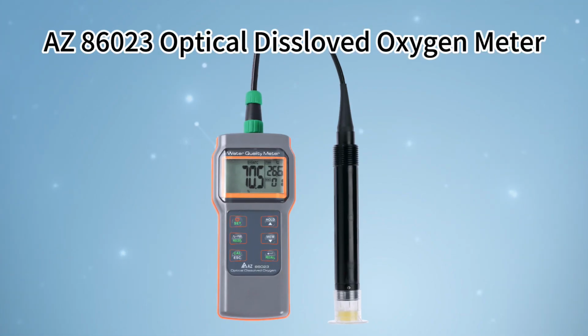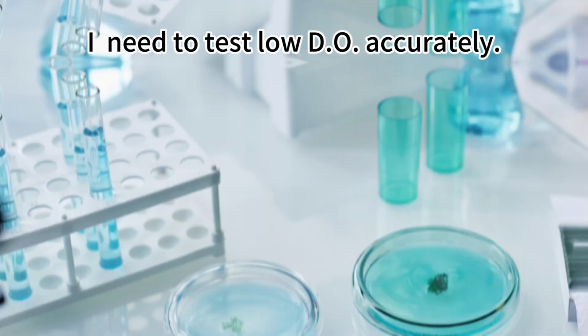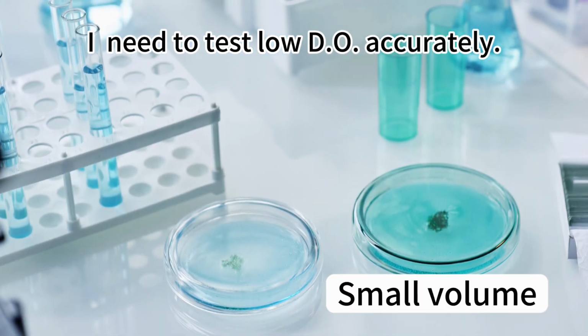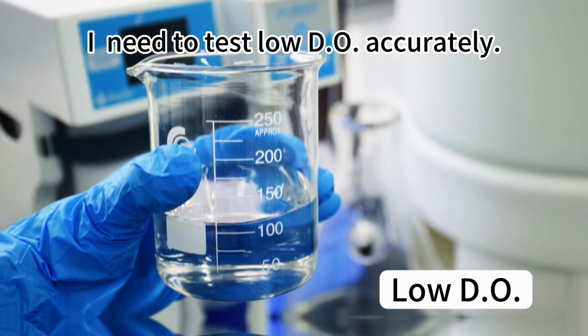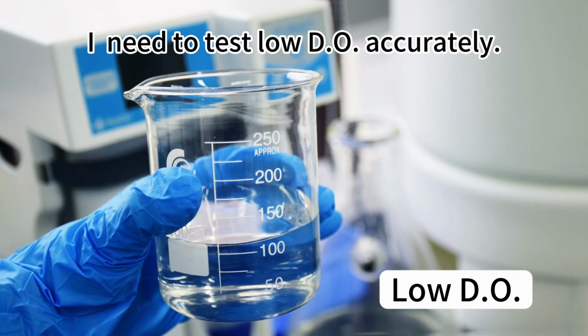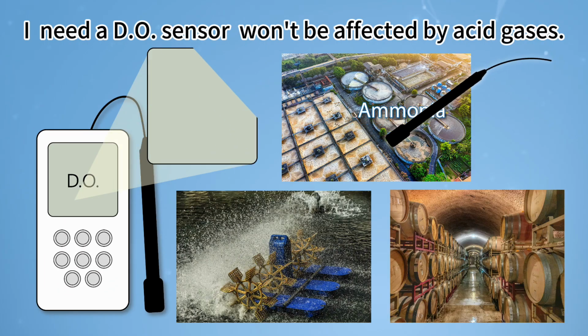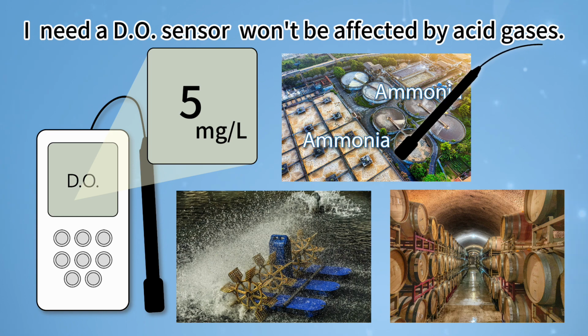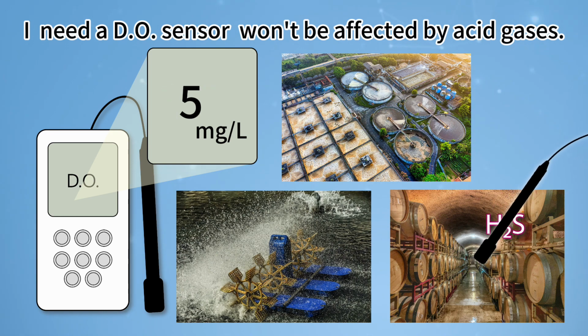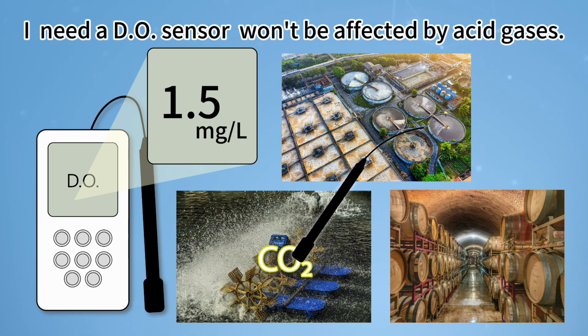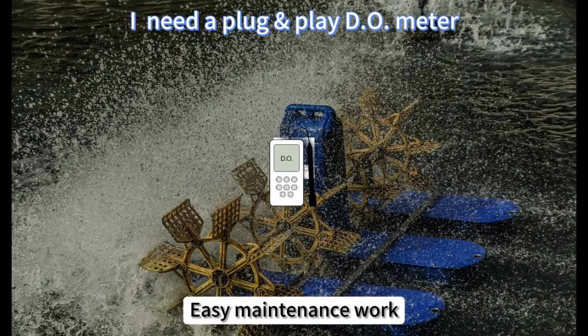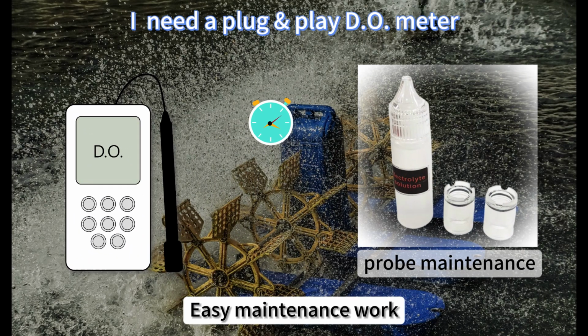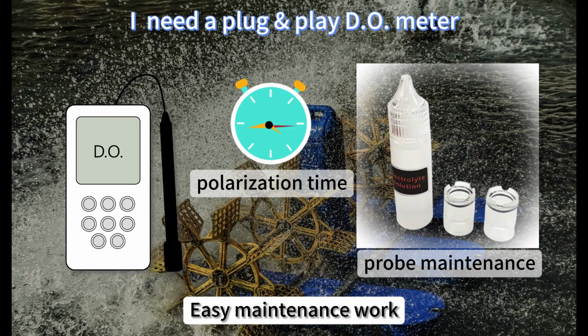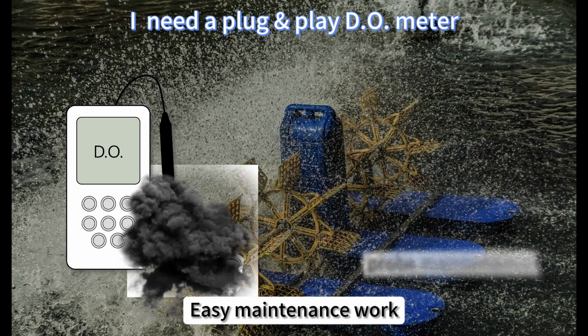AZ Optical Dissolved Oxygen Meter. My sample volume is small and DO value is low. Can I still test it without consuming more oxygen? CO2, hydrogen sulfide, and ammonia constantly affect my electrochemistry DO sensor. How to improve? Is it feasible to bypass waiting for polarization, continuously stir the probe, and probe maintenance work?